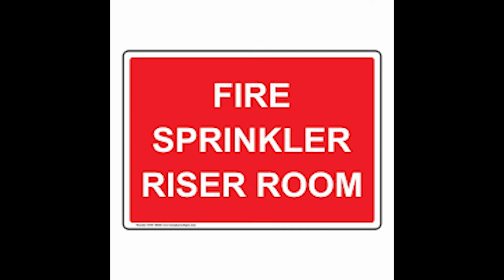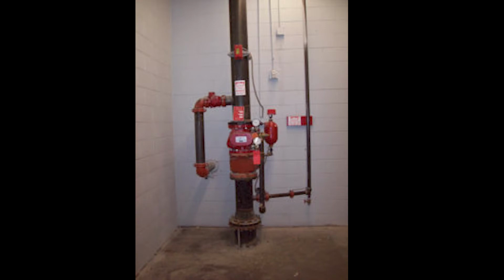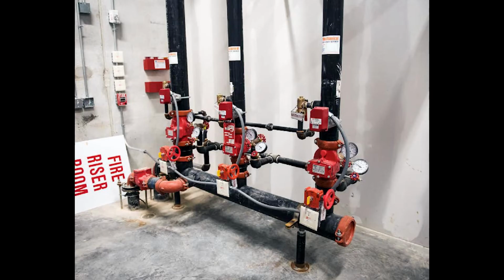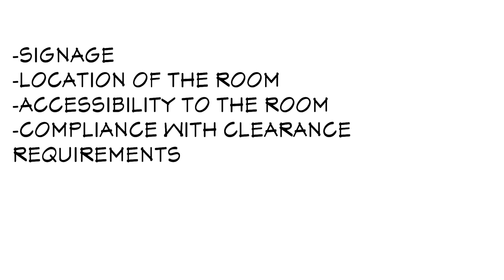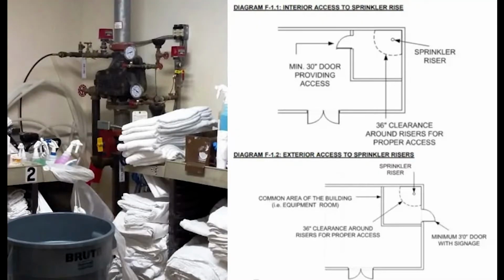The last design consideration I will cover for this video involves the use of fire riser rooms. There are a lot of complicated rules for designing a fire riser room. This is because of its importance when it comes to a life safety situation. The main concerns for designing a fire riser room are the signage, the location of the room, the accessibility to the room, and the compliance with the clearance requirements. Fire riser rooms need to have signage to help locate the room and some of the components of the fire riser unit. They should be located along the exterior wall, usually with an exterior door so that workers and emergency personnel don't have to enter the building to access the fire riser room. There are also clearance requirements meant to allow enough space for the workers to safely remove some of the larger components such as control valves and alarm check valves.